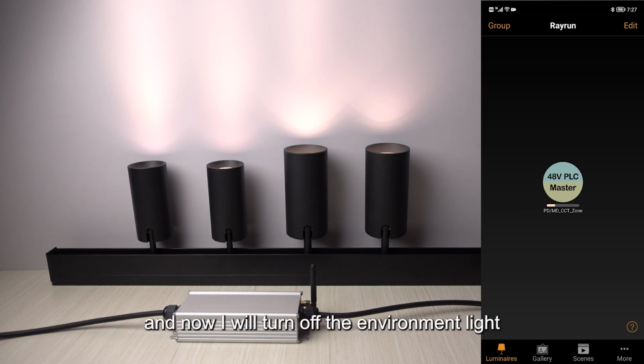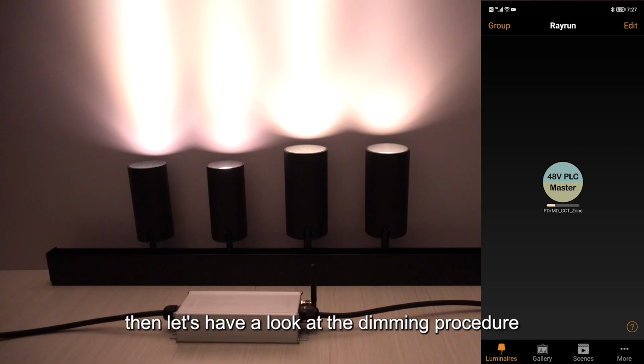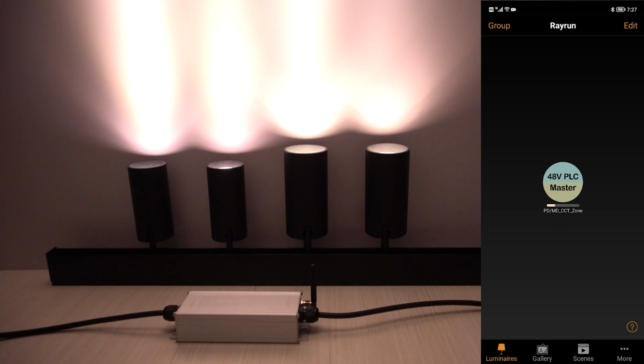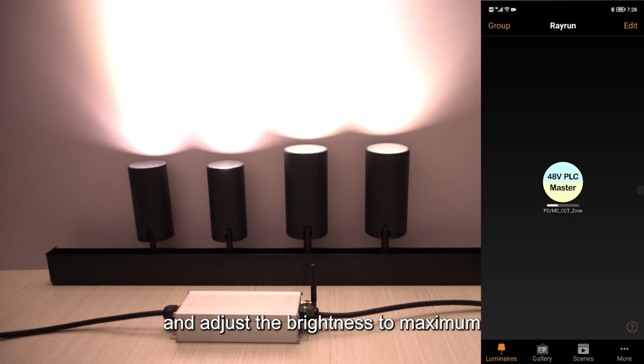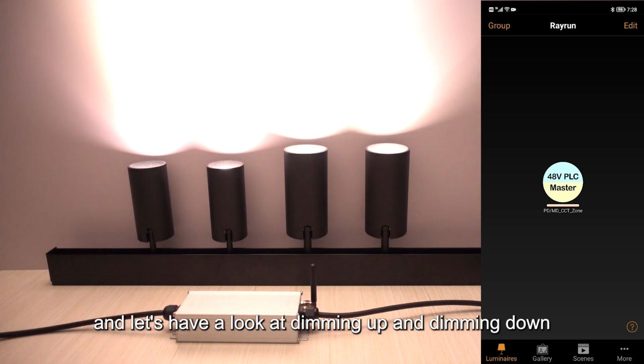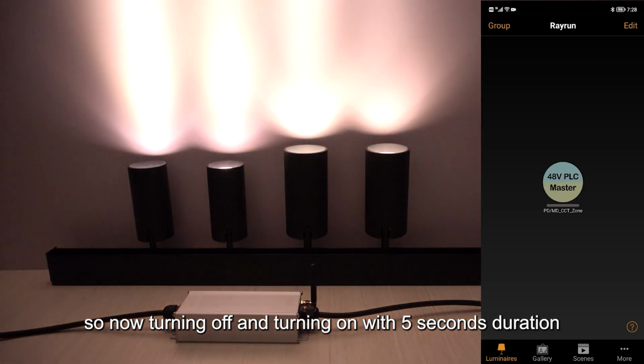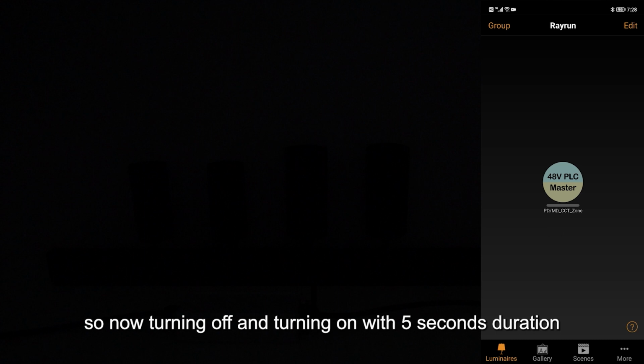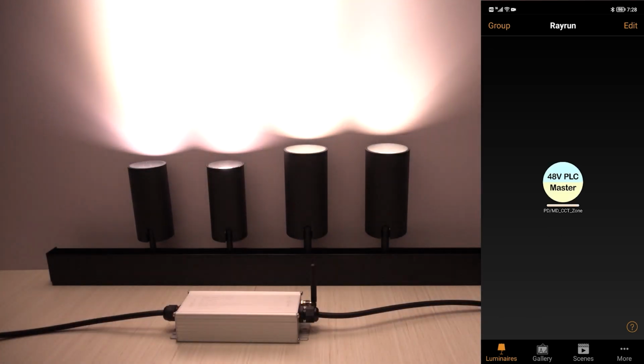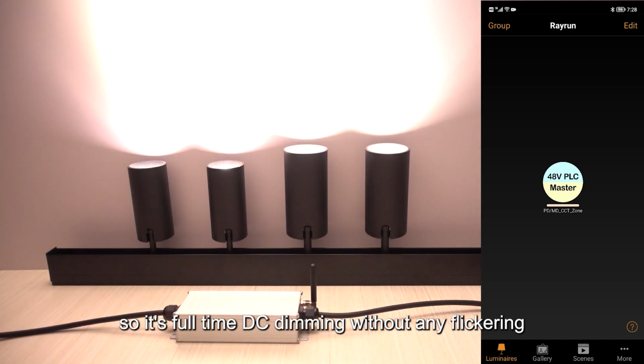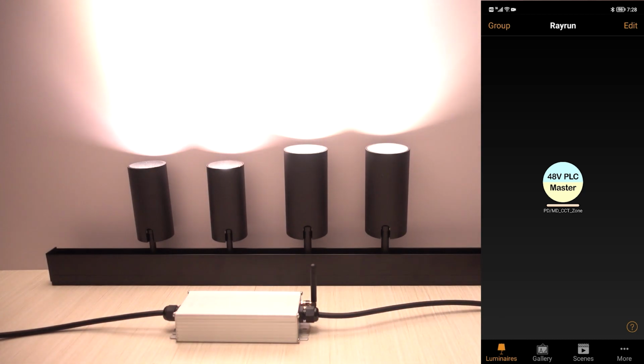And now I will turn off the environment light. Then let's have a look at the dimming procedure for the duration of 5 seconds. Now I lock the exposure setting of the camera and adjust the brightness to maximum. And let's have a look at dimming up and dimming down. So now turning off and turning on with 5 seconds duration. So it's full-time DC dimming without any flickering.